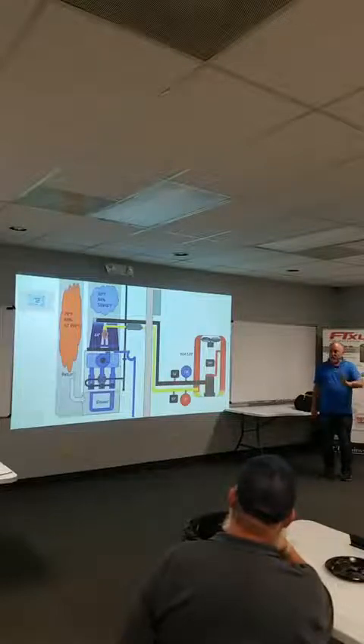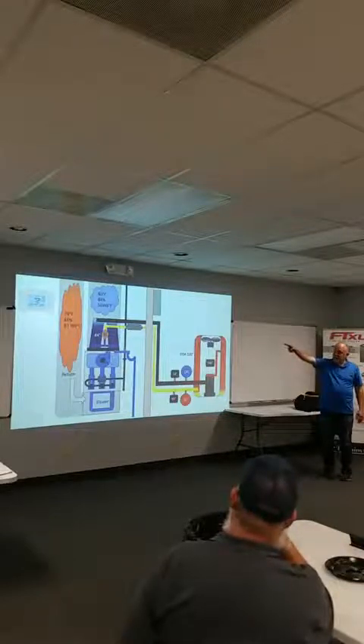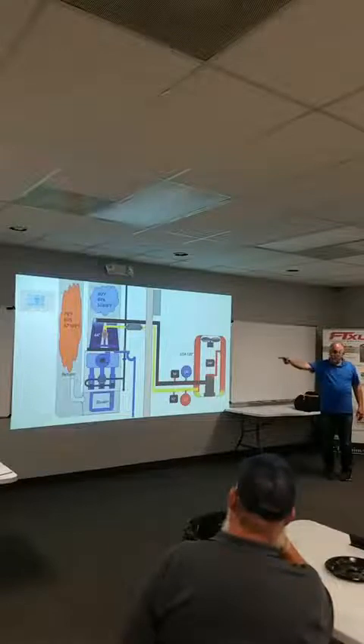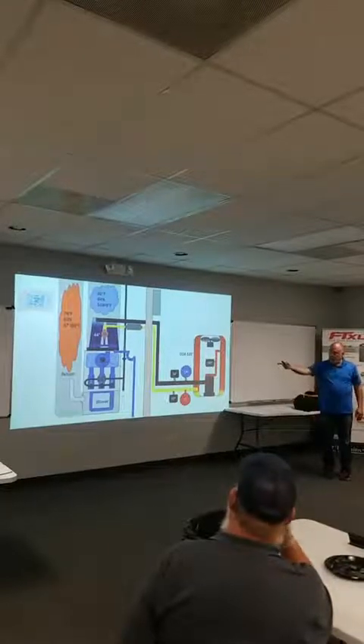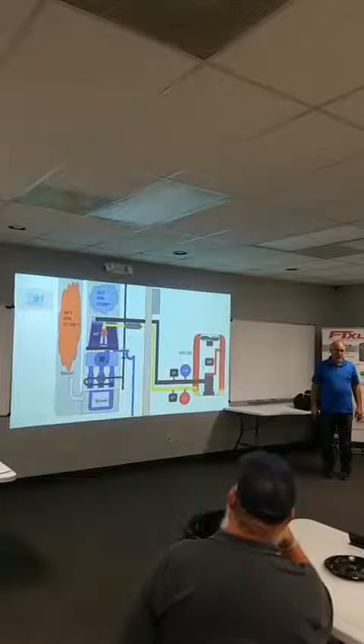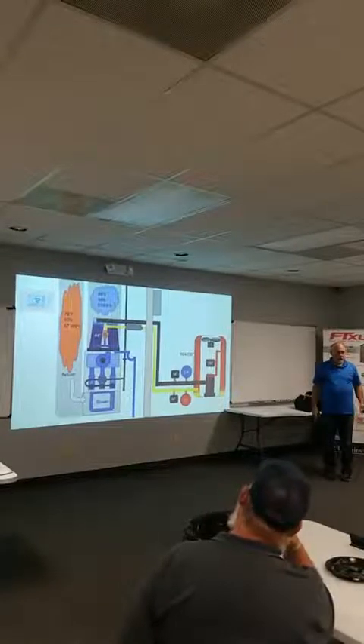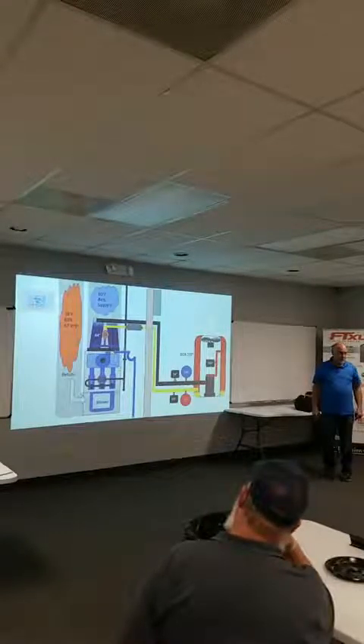When I walk down here, I look for the thermostat, I see what the thermostat is. So in this case, it's 72. I go upstairs and I measure, or in my furnace room or whatever, and I measure 78-degree return air, right? That's a pretty good sign of what? Duct leakage. You're pulling hot air from somewhere.